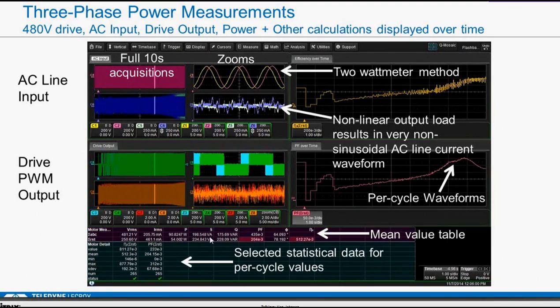These measurements are made on the full spectrum of the acquired signal. If I had filtered it to a harmonic, you'd see some very different values for power factor. And note throughout this conversion process, the input-output conversion is about 50%. In this particular case, with this load, the conversion gets better as you go higher in amperage. Now, these values are mean values throughout this whole acquisition.